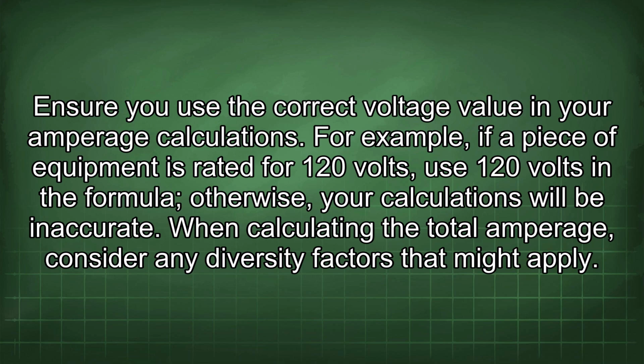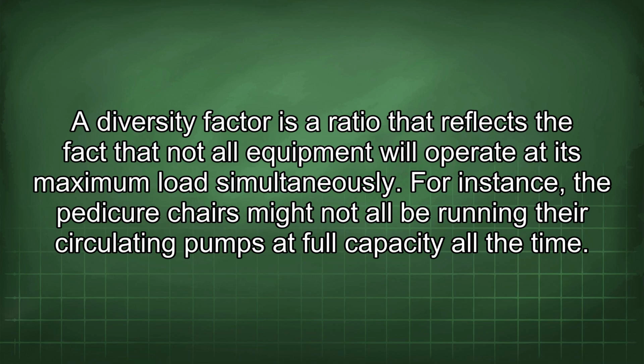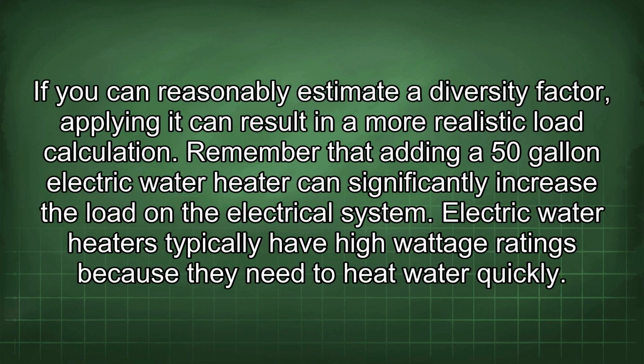When calculating the total amperage, consider any diversity factors that might apply. A diversity factor is a ratio that reflects the fact that not all equipment will operate at its maximum load simultaneously. For instance, the pedicure chairs might not all be running their circulating pumps at full capacity all the time. If you can reasonably estimate a diversity factor, applying it can result in a more realistic load calculation.